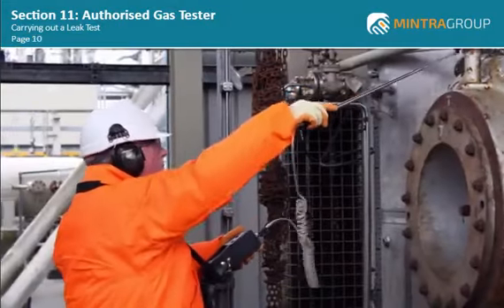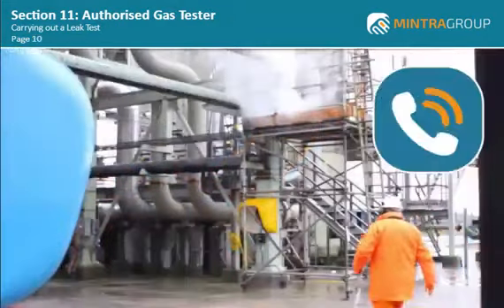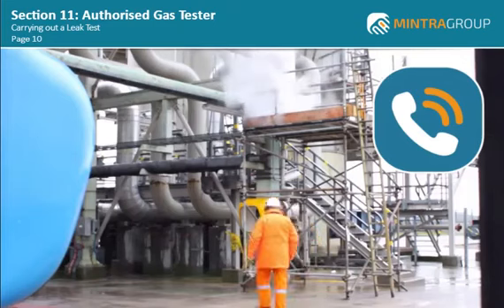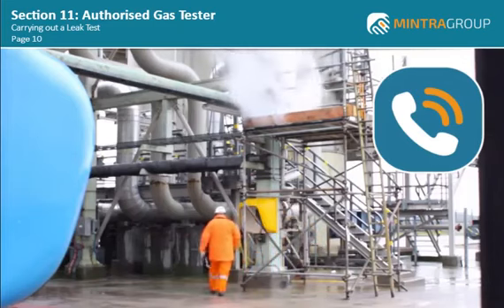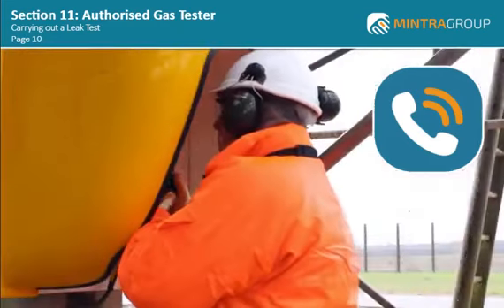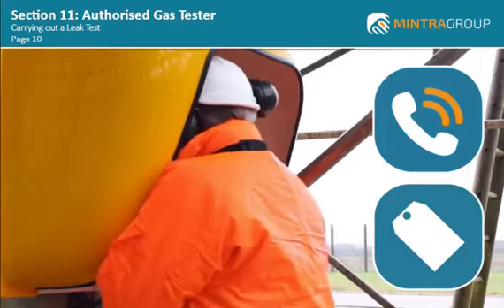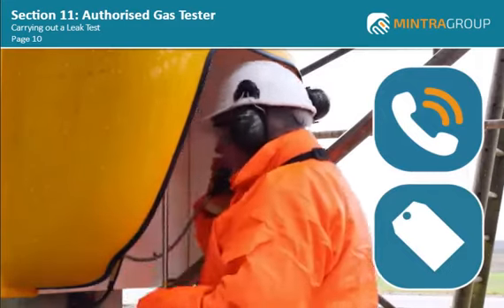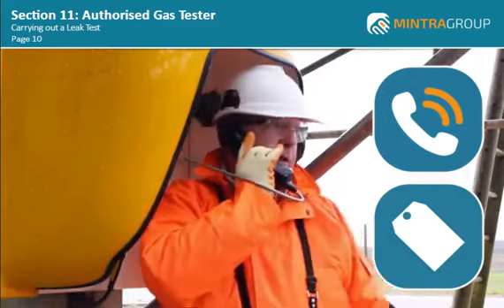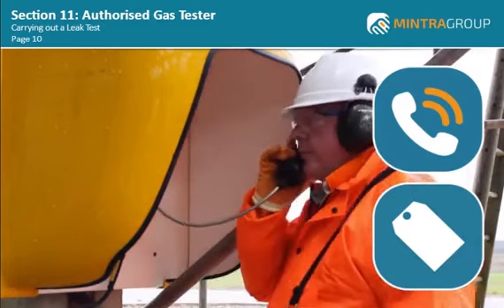If a small gas leak is detected, inform the control room and note the nearest tagged instrument or valve for a reference point. If possible, place a tag in the area of the leak so that the operations personnel can quickly identify where remedial action is required.